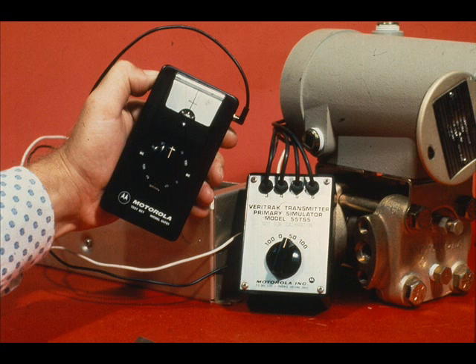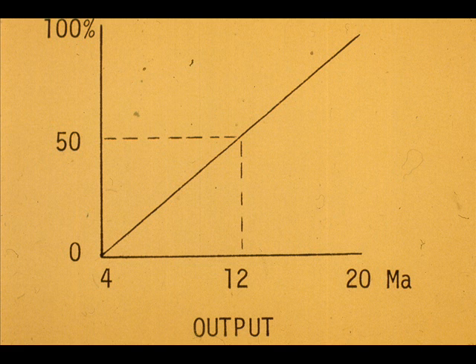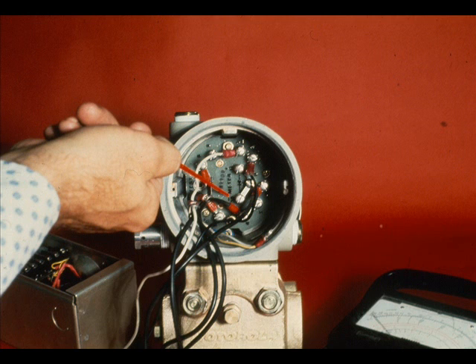The 50% setting provides an approximate 50% input check. The amplifier output should read approximately 50% of span. The 50% selection also gives a quick check on the approximate linearity of the transmitter. If desired, a milliamp meter can be connected across terminals 10 and 11 for reading the transmitter output.